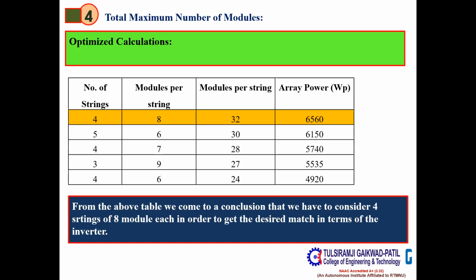I have just taken a problem statement with the help of the data sheet which is available from the solar PV module manufacturers as well as the inverter manufacturers. You can take such problems with you as a project. You can size your system as a project, because again, these are the ideal calculations. When you go to a particular site, you will check the rooftop size of your client, because every time your rooftop would not be even, right? Even in the sense, it would not be square, it would not be rectangle, sometimes it would have some altogether different shape, right? So in that case, you should be in a position to justify your requirement of the client, and you should be able to actually size your system according to the requirement of the client.